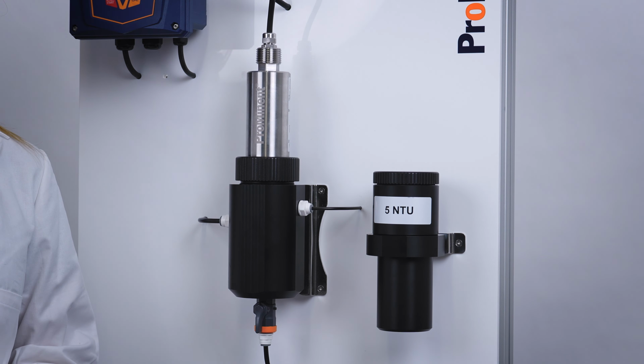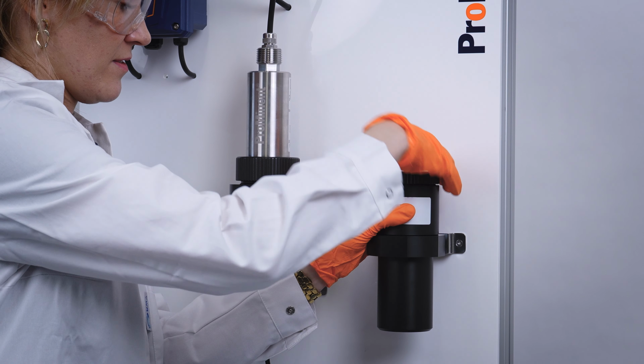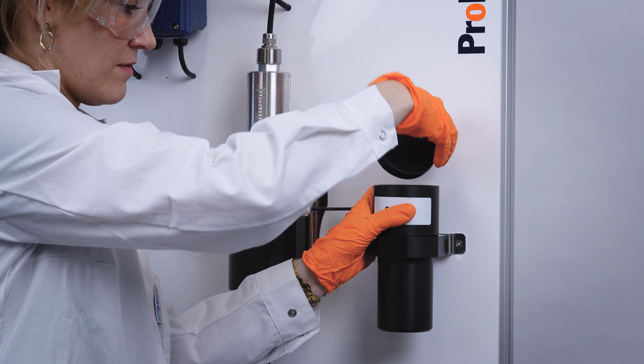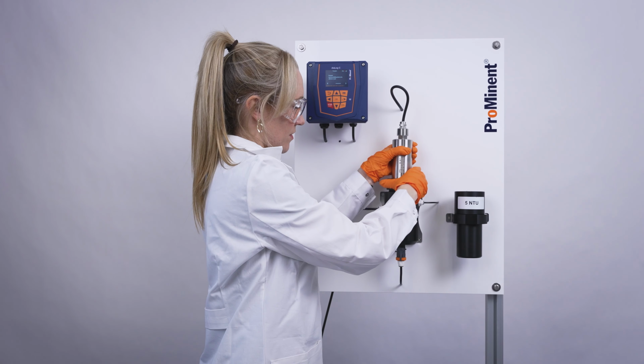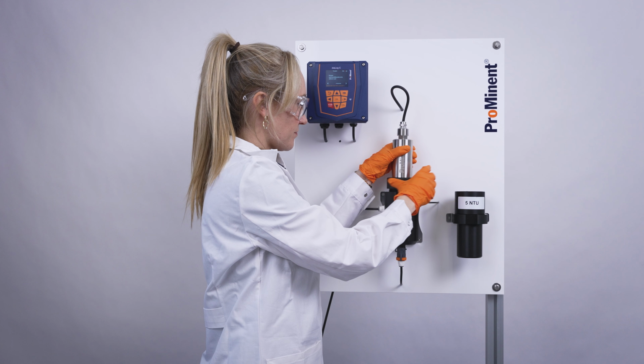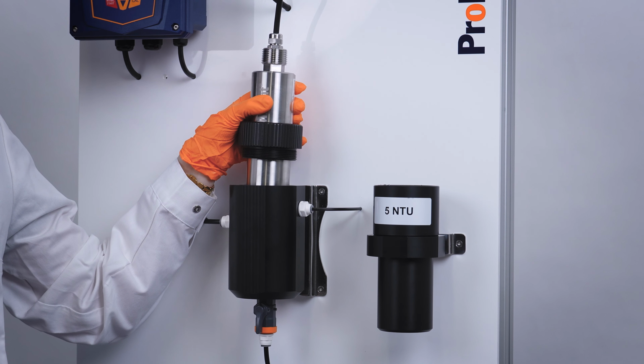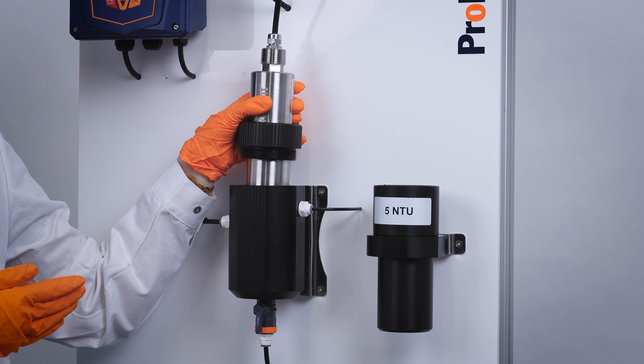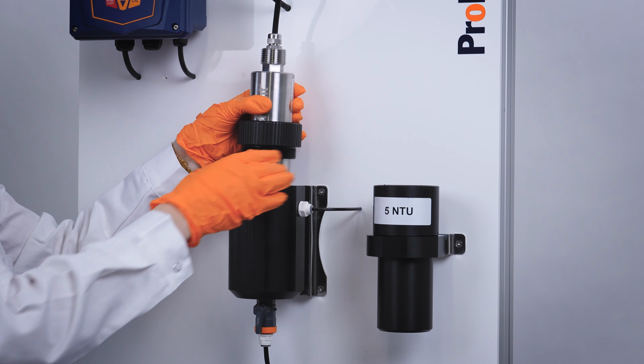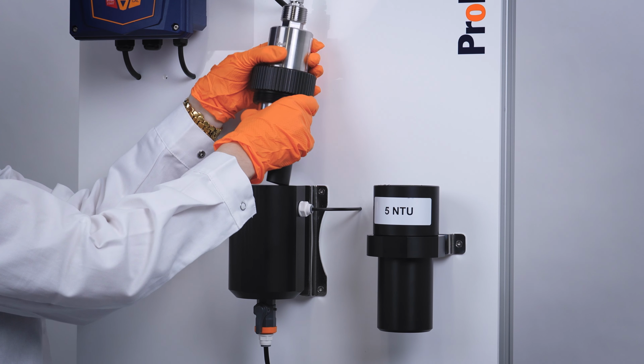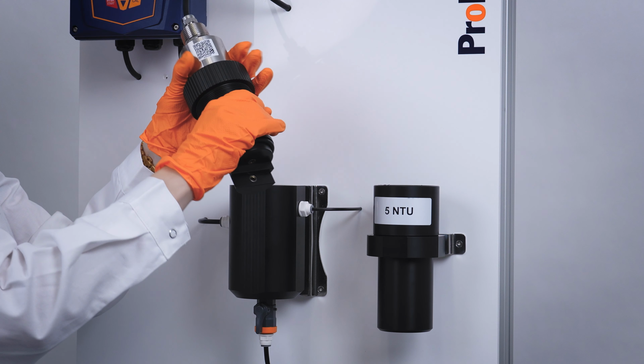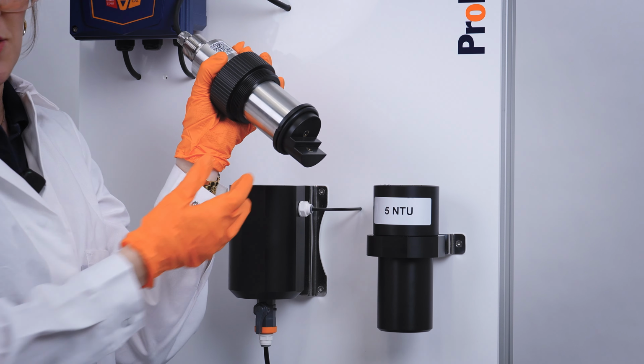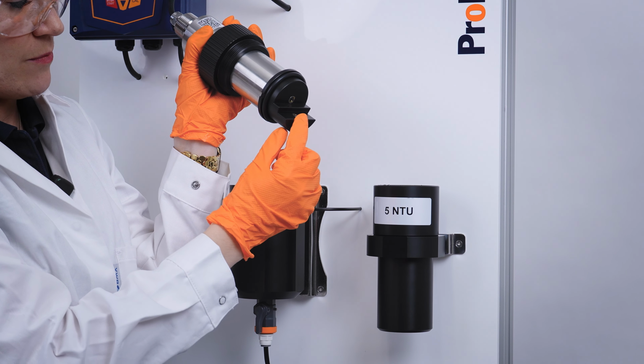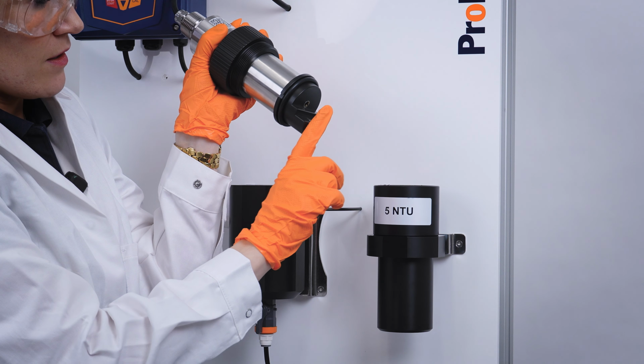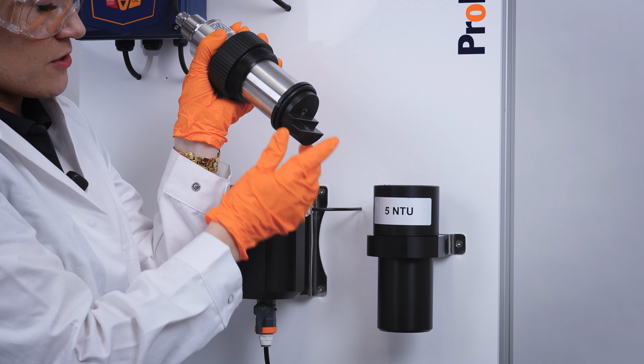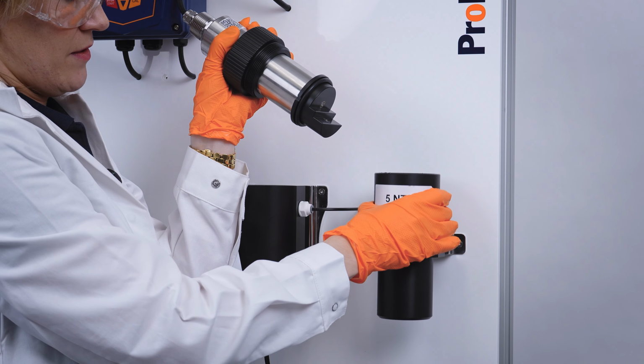So now we open the lid. Open the locking ring. And of course you have to make sure that the sensor is clean. I prepared it just before, so that's fine for now. Take the sensor, turn it, and then you have to make sure that the window from the detector looks in this direction. And then you take the calibration vessel.